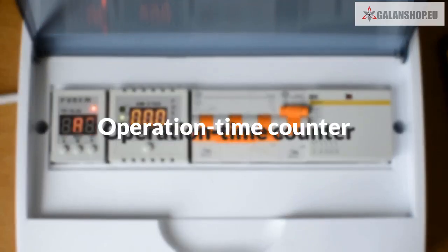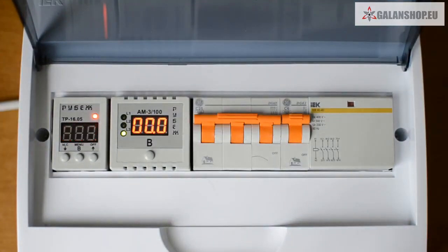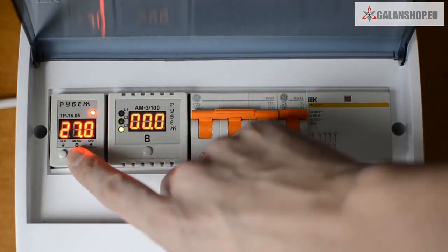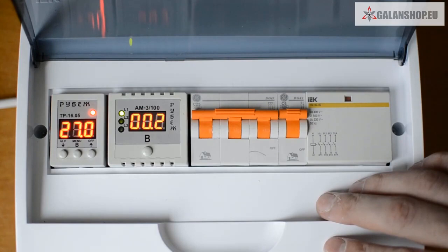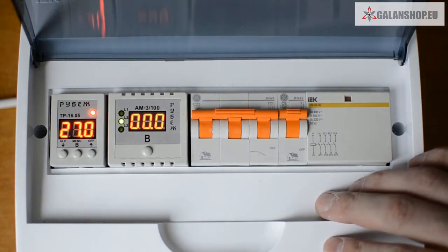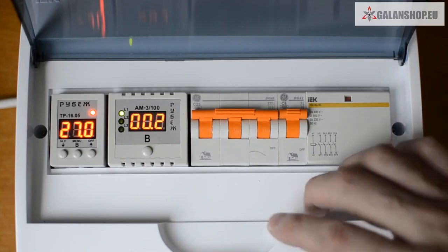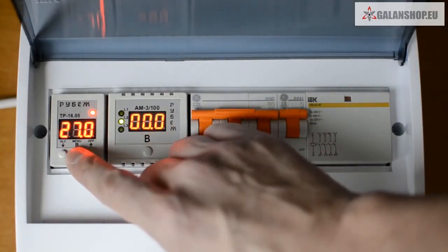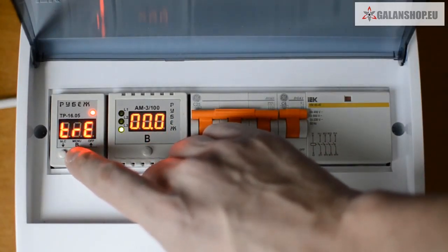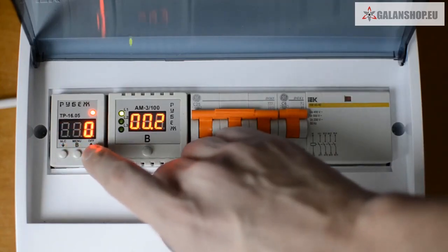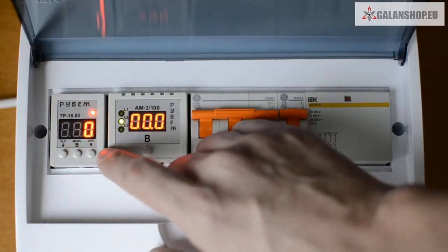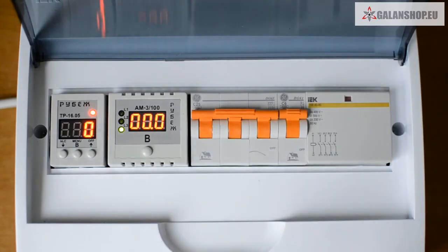Operation time counter. This model of heat controller has a built-in operation time counter. The time is calculated every second of the heat controller's operation and is saved in the device internal memory every 15 minutes. Even in case of a power cut, data is stored in memory. The calculated time is recorded in a heat controller's TRE menu in increments of 1 hour. The maximum recorded value is equal to 999 hours. When the maximum value is reached, the time count stops. You can resume counting by resetting the counter.